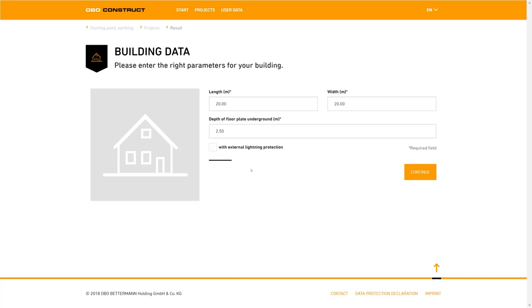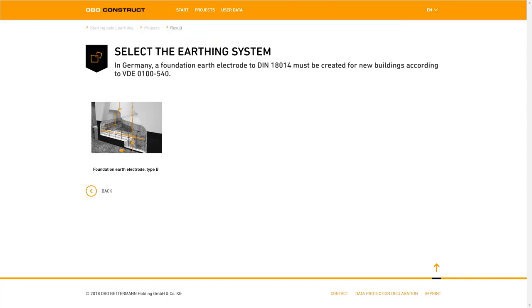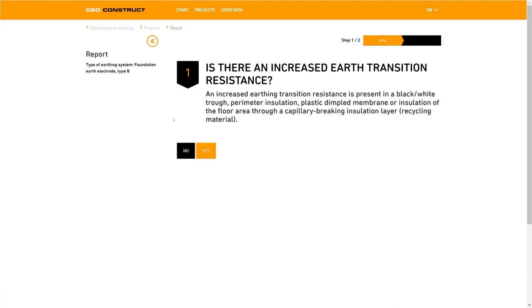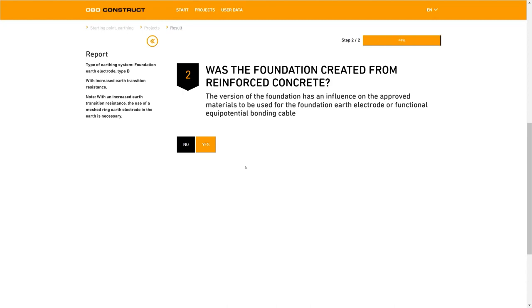The standard DIN 18014 requires a foundation earth electrode. The foundation earth electrode that we will select now is called type B. In the next step you'll be asked if there's an increased earth resistance, for example due to a white trough, black trough or due to perimeter insulation. If this is the case you need to confirm here with a yes. You will have the appropriate information available, such as which concrete you've used or if further insulation layers will be added to the foundation.